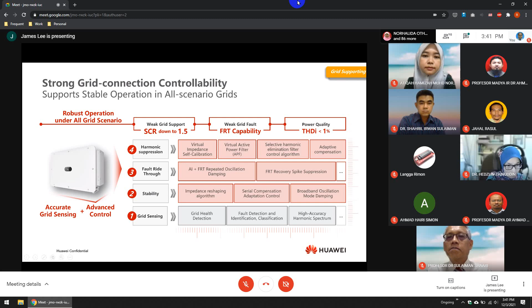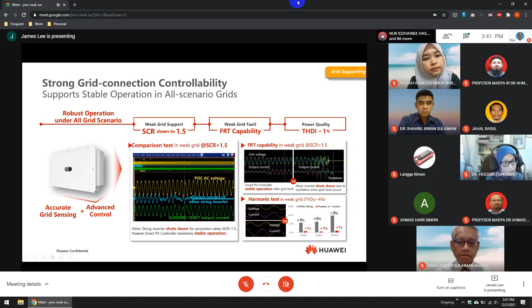Here is some comparison testing that we did in a weak grid. So I'll jump now to the case study itself. In China, there was a particular plant that was 100 megawatts, and they added our PV plant of 20 megawatts. You can see the SCR calculation: before the additional 20 megawatts it was 2.17, and after the addition it went down to 1.85. During this time there was a low voltage ride-through event, and the entire system tripped, whereas for our system, it was able to ride through it.